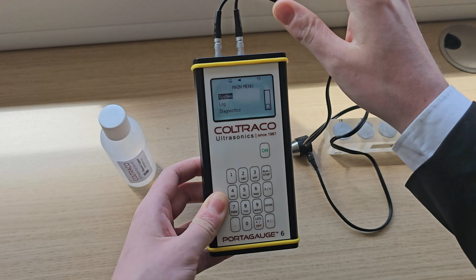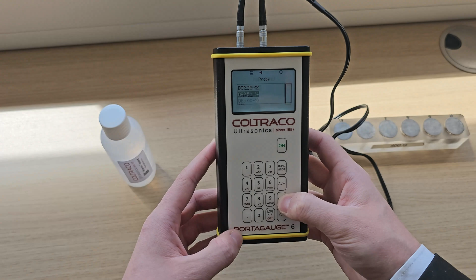So to start with, I'll show you how to take simple thickness measurements. So I'll turn the device on. I will connect the two LEMO connectors into the top of the unit here. And I will go into quick start. So I can either go up on the menu to quick start, or I can just press 1 to bring me there from anywhere on the device. I'll press enter. I'll select the 2.5 MHz 14mm probe, which is what I'm using. And carbon steel is the material we have in this test block here. So I'll press OK. And the device has started to measure.